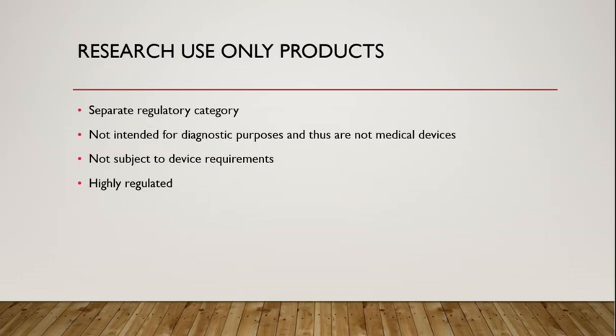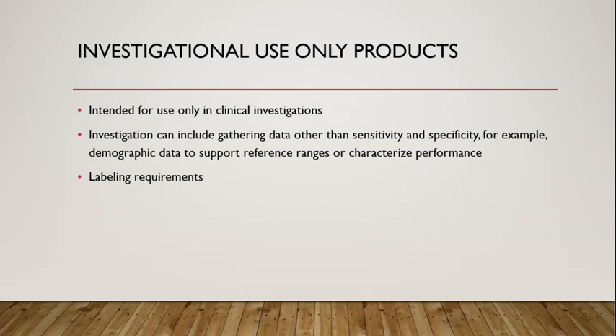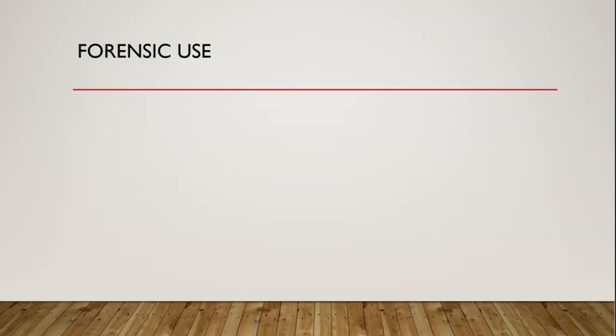It's a separate regulatory category. It's not intended for diagnostic purposes and thus these are not classified as medical devices. They're not subject to device requirements, but they are highly regulated. Similarly, there are investigational use only products, and they're by definition to be used only in clinical investigations, and that investigation can include gathering data other than sensitivity and specificity, for example, demographic data to support reference ranges or characterize performance. And there are some labeling requirements for investigational use only products.